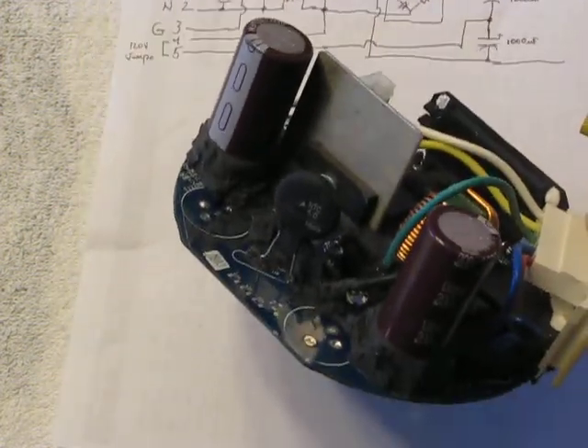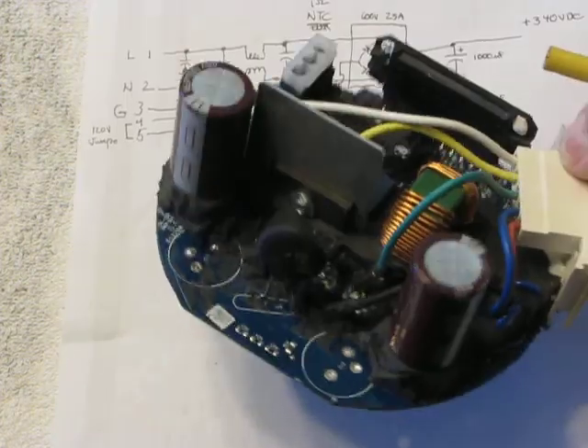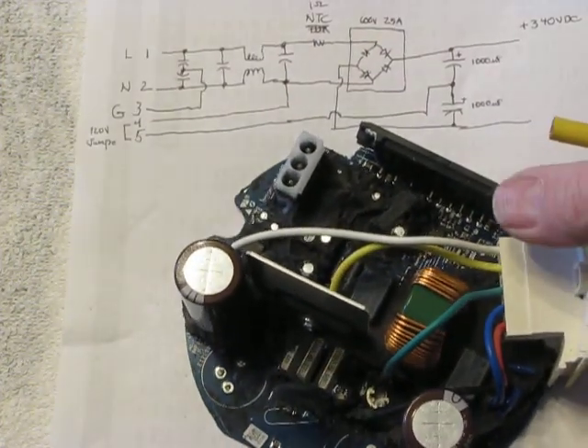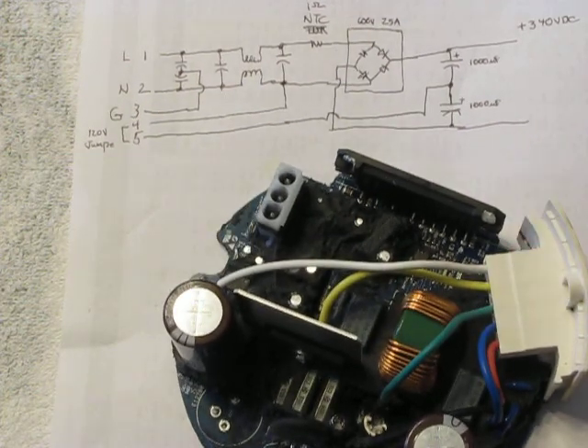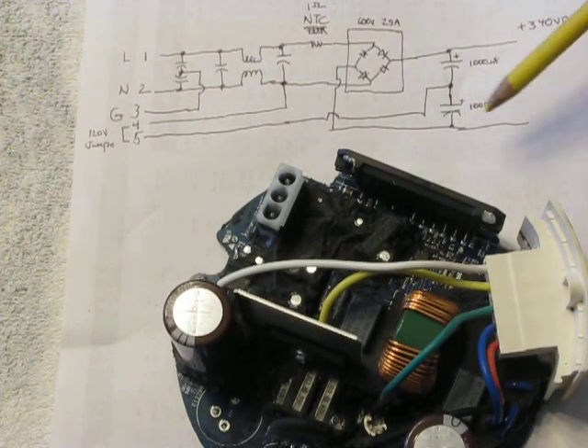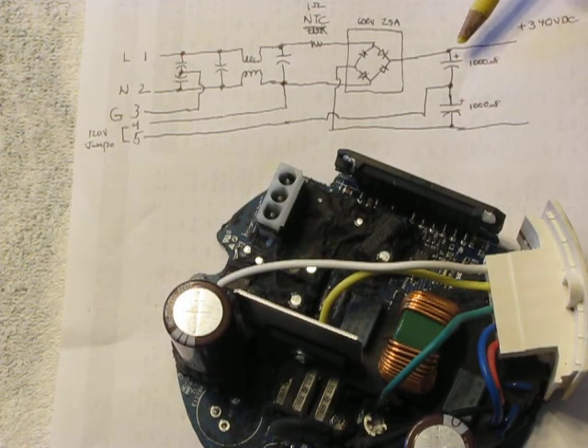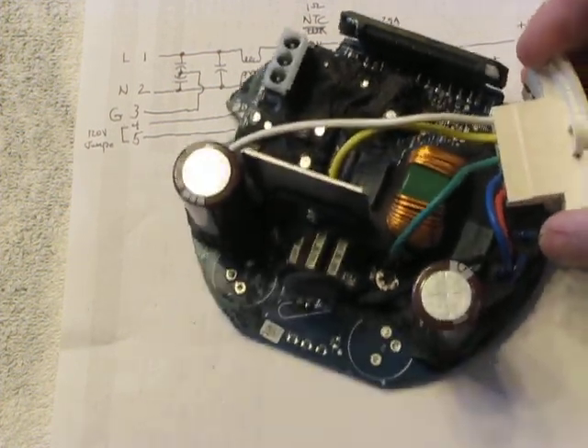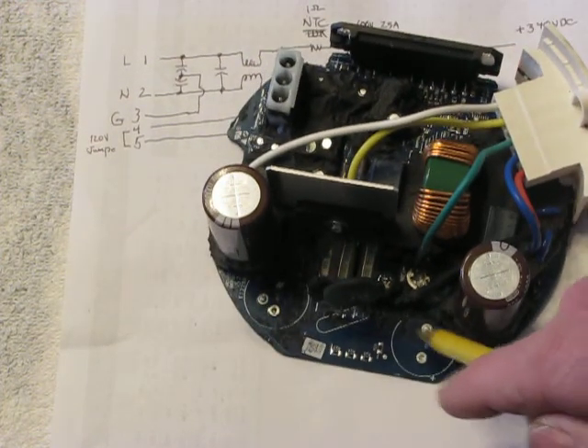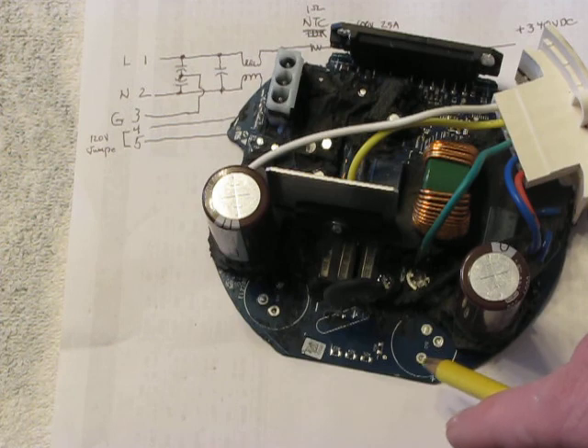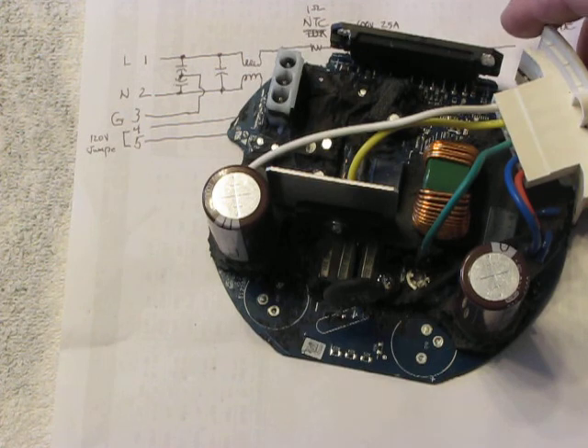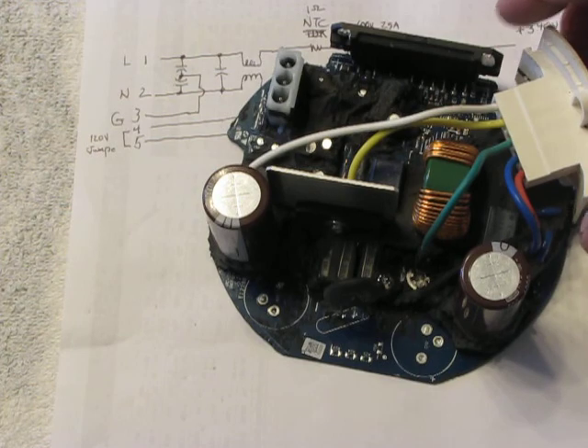And then there are the two filter capacitors here. They're actually in series because each one of them is rated at 200 volts, and the power supply puts out 340 volts DC. And you can see on the board there's spots for two more, and I believe those are used for the higher power motors, so you'd use this exact same circuit board, probably everything, and just add those two capacitors, and it'd be rated for the 3/4 horsepower.